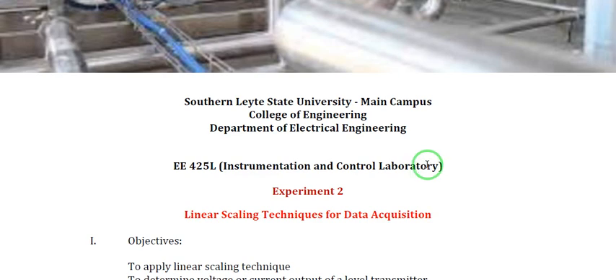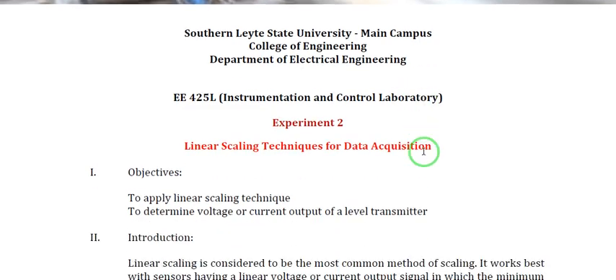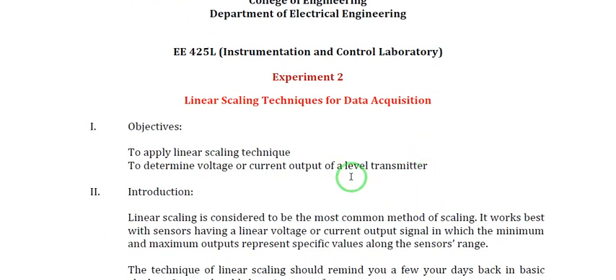Linear Scaling is one of the scaling techniques used for data acquisition, used for programming of our controller in the Instrumentation and Control System so that our controllers will be able to understand the changing in values for specific change in a variable. So in this case, in this experiment we are going to focus on the water level of a tank. So we are going to determine voltage or current output of a level transmitter. We have mentioned to apply linear scaling technique.